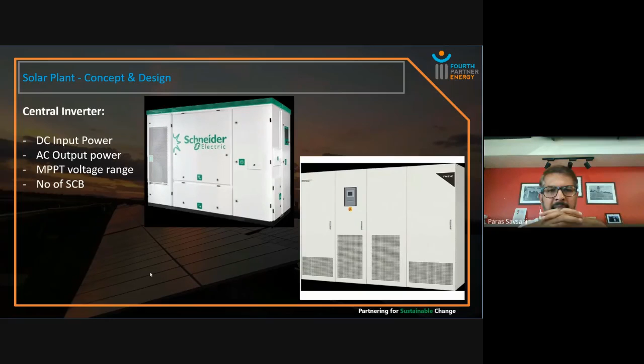So what's the commercial advantage? If you remove all the brains from each string inverter and keep a single brain at one location, combining all the strings and DC power from individual small locations across the plant, each string combiner box collects this voltage and current as power and feeds it to the central inverter. This central inverter concept combines all the brains together at a single location, making it commercially viable since you don't need a brain inside every inverter. That's one major advantage of the central type of inverter. Central inverters are mostly used for larger plants, starting from 1 megawatt and bigger.